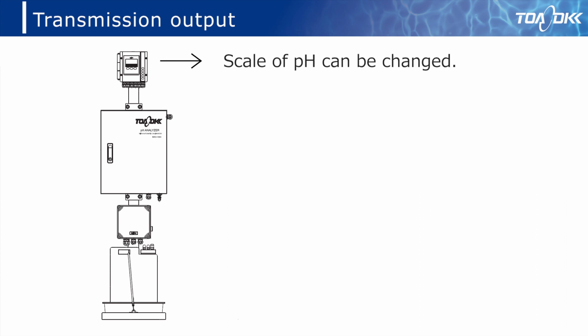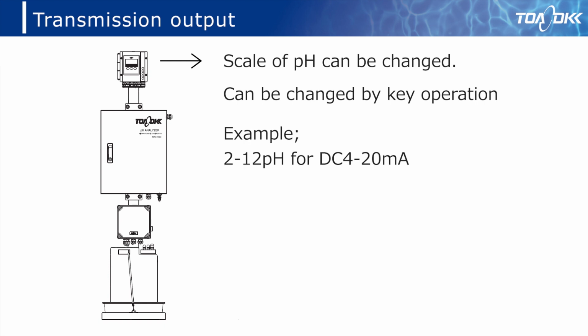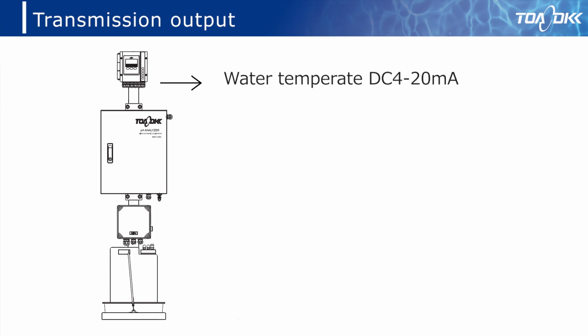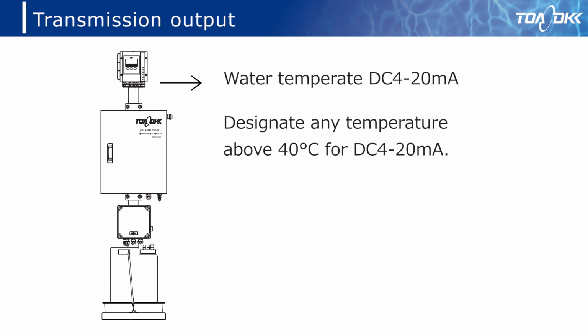The scope of pH can be changed by keying to the scale of the receiving part, such as the control panel. For example, 2 to 12 pH can be used for DC 4-20 mA. Water temperature can also produce transmission output. For DC 4-20 mA, it can be arbitrarily set in a 40 C width or more. For example, 0 to 50 degrees Celsius can be set.